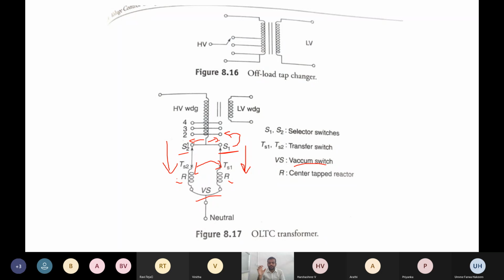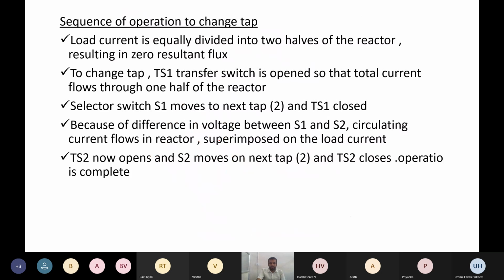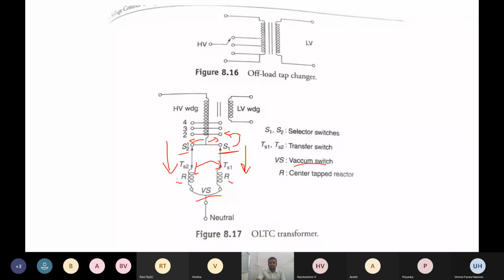Because of the difference in voltages between S1 and S2, a circulating current flows. Normally what happens here, a circulating current flows in the reactor and that will be imposed on the load current. So here a voltage difference is created. The voltage difference will be created between the switches.